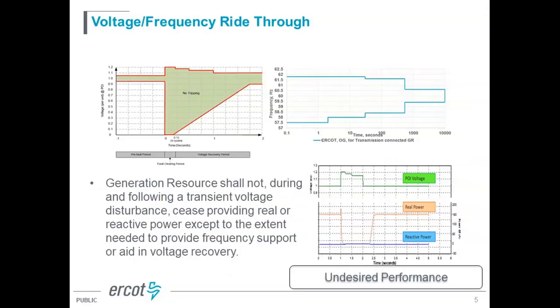The previous two are more from a steady-state normal operation perspective. During the dynamic or during the disturbance, all the IBRs also need to have voltage and frequency ride-through capabilities. And to follow up on what Ryan mentioned earlier, momentary cessation is also not allowed for resources connected to ERCOT. During the initial interconnection study process, we review and examine the model capability and also circulate with the owner to emphasize all the requirements, and ensure those capabilities can be provided and the undesired performance can be addressed or even eliminated before they connect to the ERCOT system.